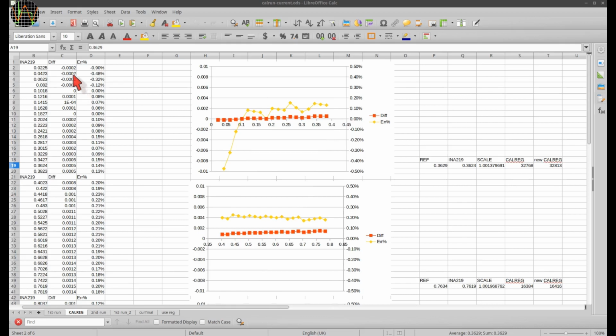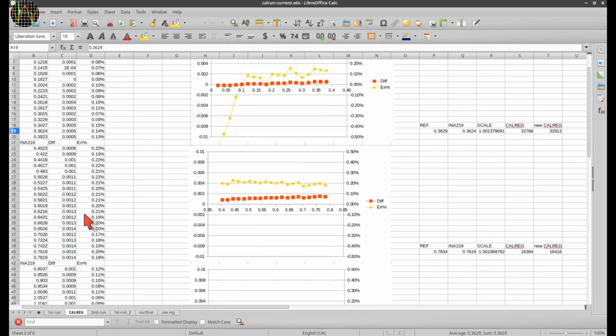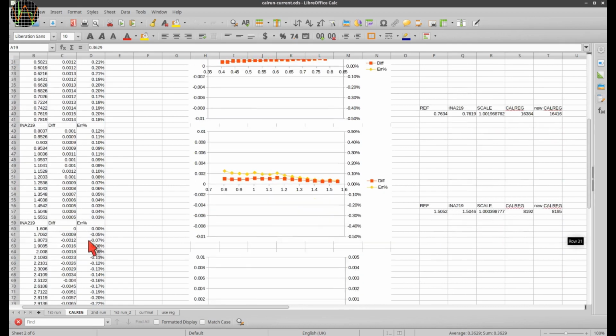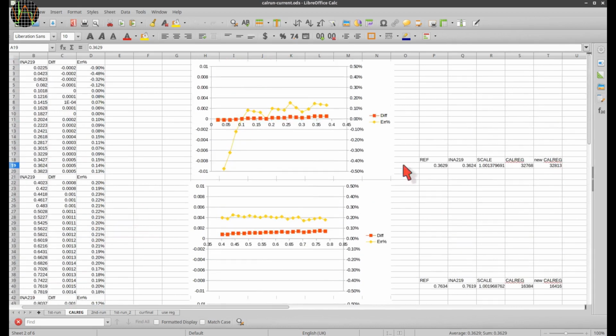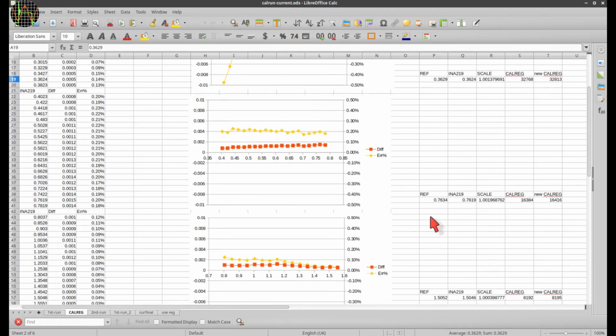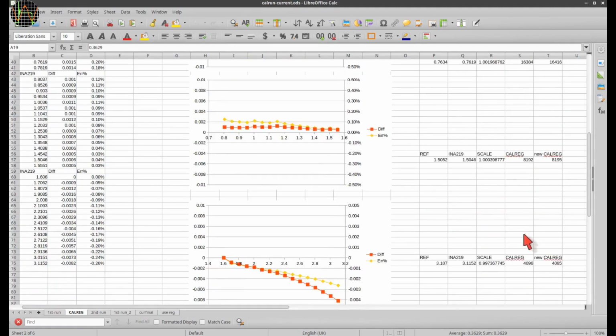Here's the spreadsheet that contains all the measured currents from the 4 test runs. You recognize the graphs, of course, but what I want to show is the right side. I picked a row with fairly high currents in range A, and you see the calculation of the scale factor and the new calreg. I did the same for each of the other 3 ranges. And then applied the new calregs by editing the CalData text field.